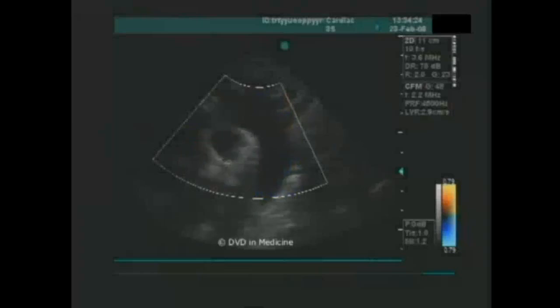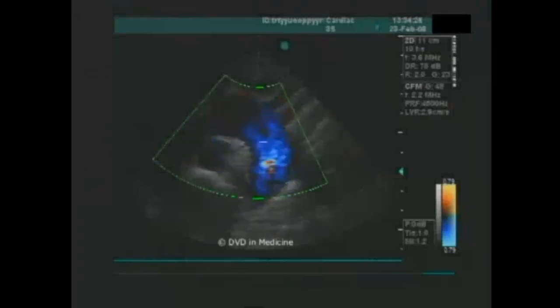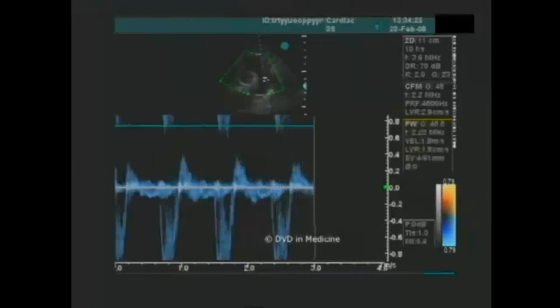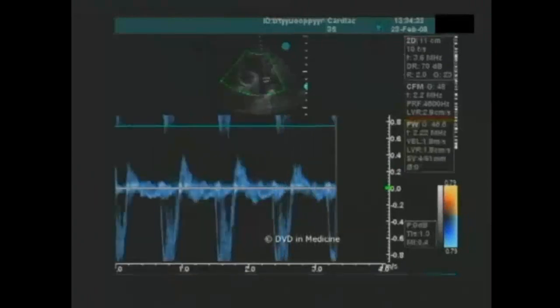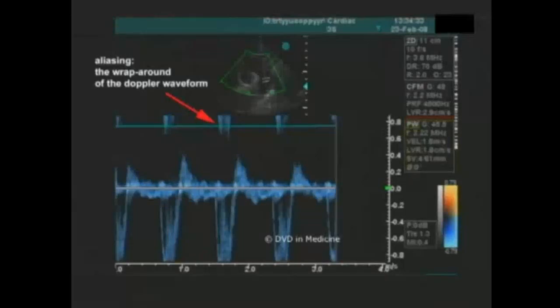Pulsed wave Doppler, the aliasing. If the pulse repetition frequency is too low for the Doppler shift frequencies from the blood flow, aliasing will occur. As a result, one sees the wraparound of the Doppler waveform. One way of removing the aliasing is to perform the corresponding shift of the baseline.